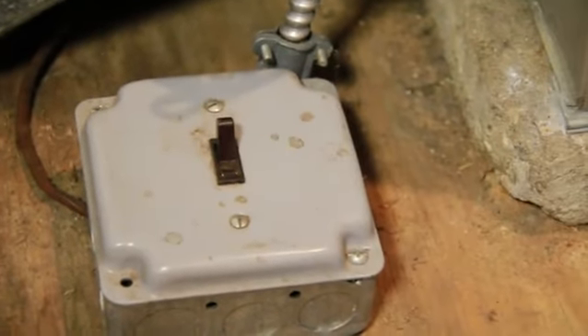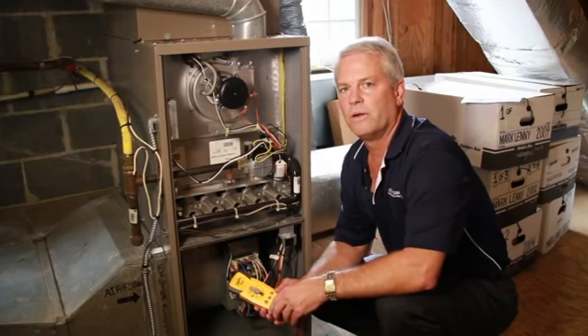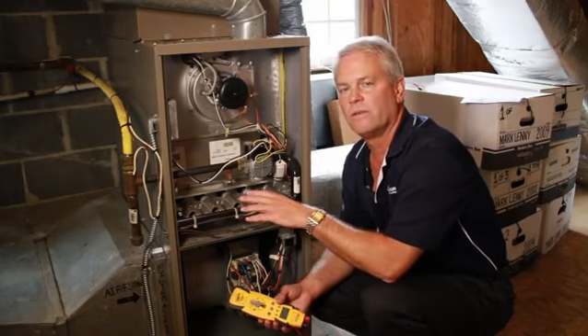It may have gotten turned off in the summer season. If you still don't hear power coming on, you want to make sure that the gas valve is on to the gas furnace, bringing gas to the gas valve itself.